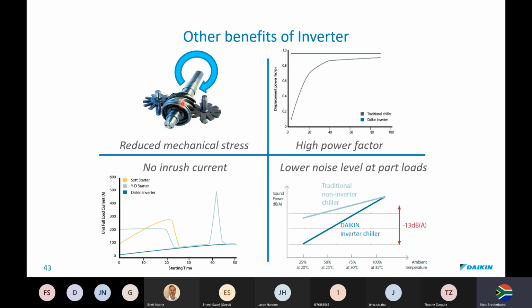So your oil doesn't get as dirty as quickly because there's less wear metals. We have a very high power factor, which may be a bit of a foreign sounding word to some of you. But pretty much what power factor does is we need to generate extra power to energize electromagnetic fields within the stator. But because we have permanent magnets in our rotor configuration, we don't need that reactive power. So we free up the transformer.